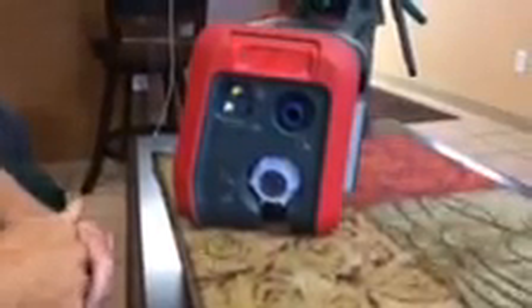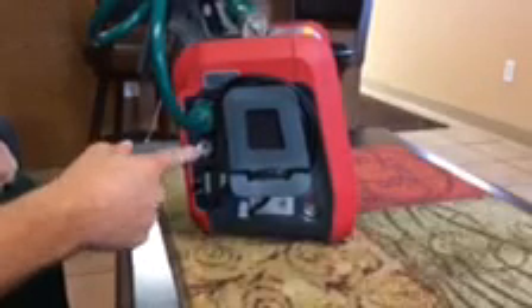If you move around to the opposite side of the ventilator, you have your air filter. This is just for entrainment air. This is where the ventilator gets its cooling air from. You have your high pressure 50 psi hosing. You have your power cord, which connects here, and again we recommend you do keep that plugged in. And then down here you have a port where we can run this ventilator off a low flow oxygen, but we chose not to do that as an option. We prefer you to use the high pressure tubing in all circumstances. I think that's all.